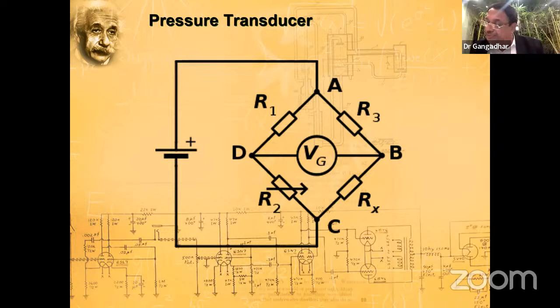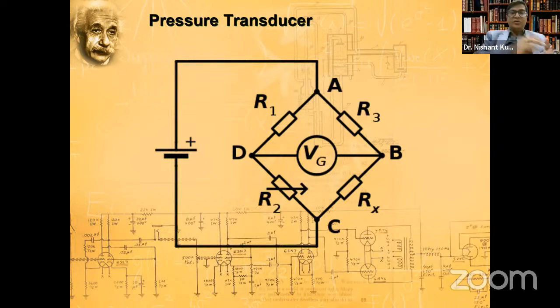Yeah, please. Okay. So the pressure transducer is the one that we use for invasive monitoring. It is based on a very simple principle of the Wheatstone bridge or the strain gauge, where we have 4 resistors. Remember in class 12, we did extensive experiments in physics where we had to find the unknown resistance. It is the same. We have R1 and R3, and the voltage is supplied here. These are in parallel and these are in parallel. These 2 resistances we know. The third one is a variable resistance, which we calibrate according to the pressure. And the fourth one is the unknown resistance, or the patient's pressure that we have to measure.